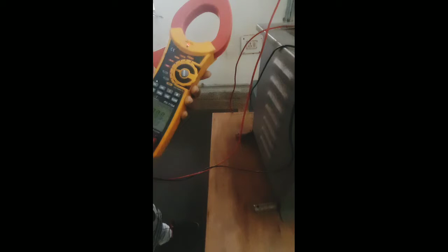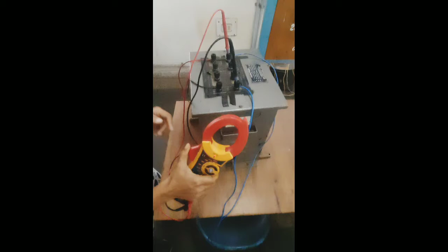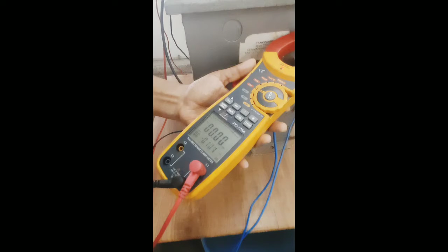In a similar way we can check the secondary reading, that is, the power taken at the secondary side at no load. I have connected the probes to the secondary terminals, and this is the reading at the secondary side, which is 0 kilowatts because it is not connected with the load.